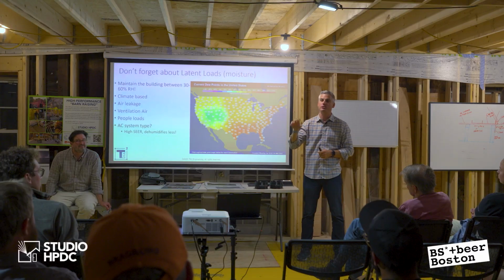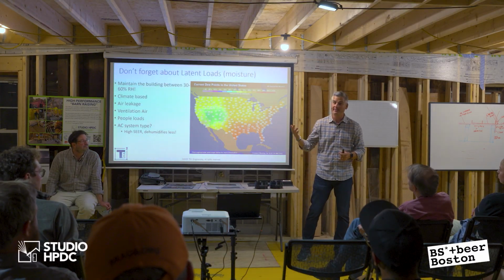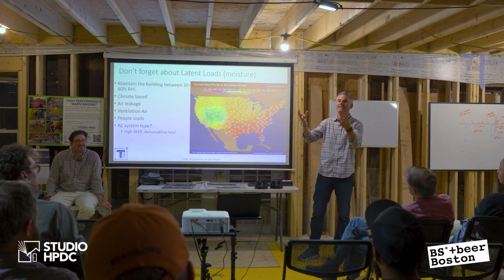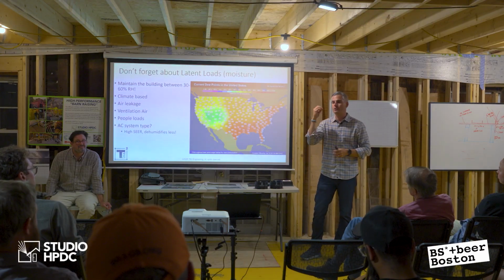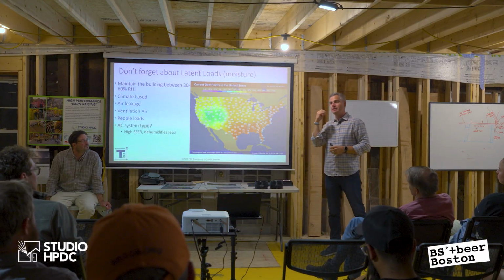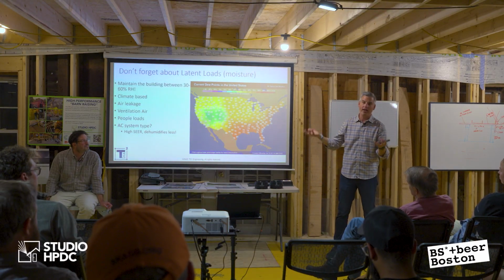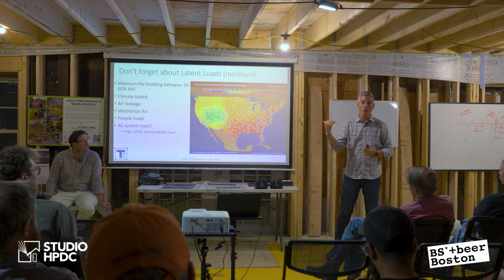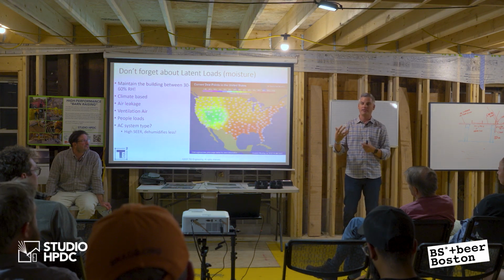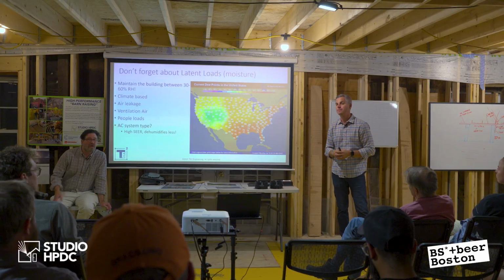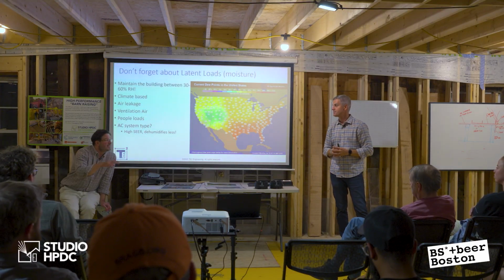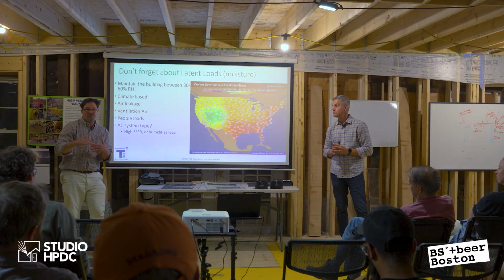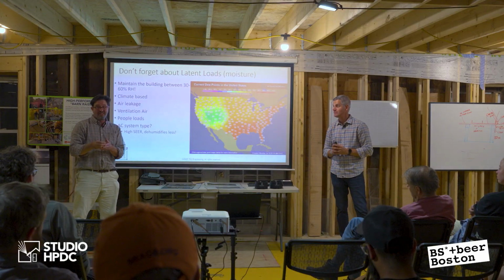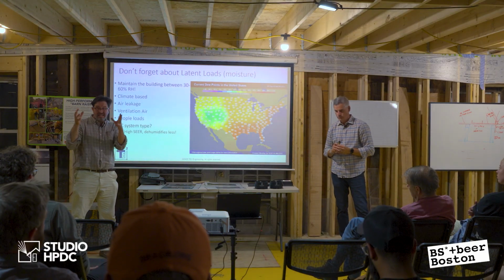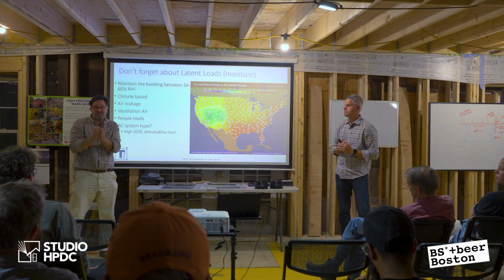So latent capacity is a Latin term for hidden. It's hidden, right? We can't see it. It's there, but it's hidden. So latent capacity is hidden BTUs that are stored in the water vapor in the air. And so we need to wring that moisture out. We need to dehumidify, and that's the latent capacity of that space. One additional point to that is the phase change is what we're looking for, vapor to water, right? So it's going to give up a lot of heat. It has to give up a lot of heat to condense into water.